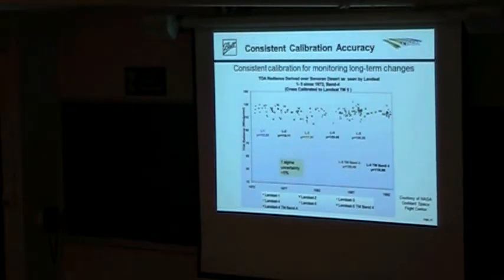Obviously, we have to have a standard such that the radiometric accuracy that we measure is consistent, so you can monitor change. If you don't have good calibration, then you can't monitor change. And so this is a chart showing the total top of the atmosphere, TOA, radiance. In other words, it's what you would see basically from the solar irradiance at the top of the atmosphere without any atmospheric effects. And that's where the calibrations are done.